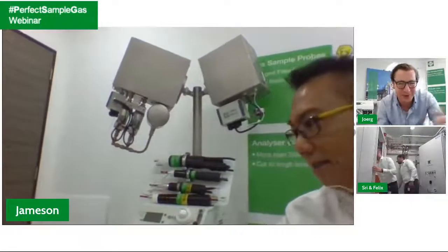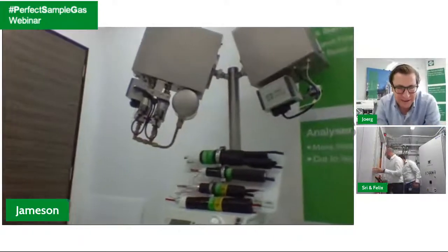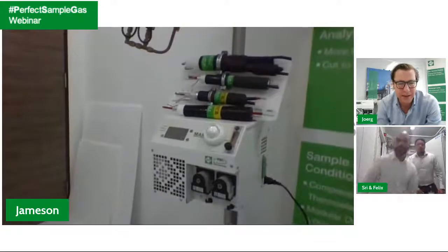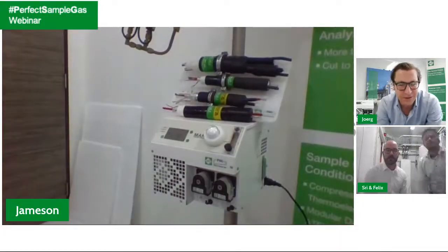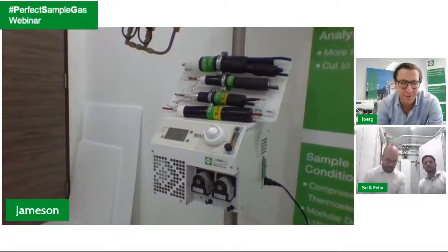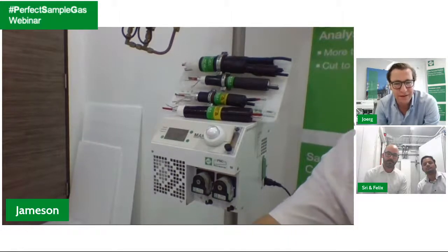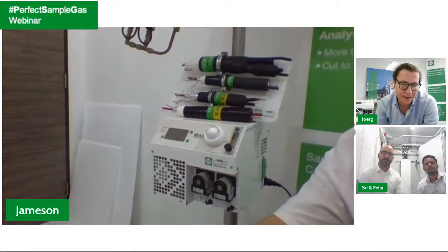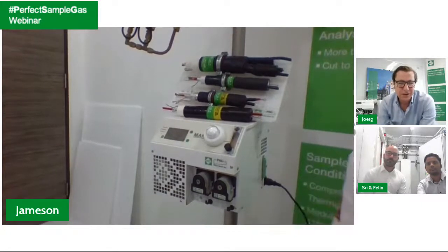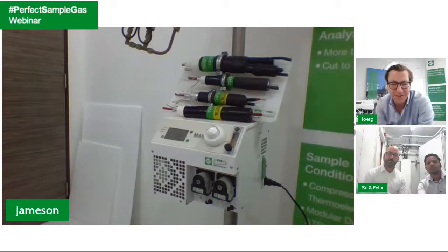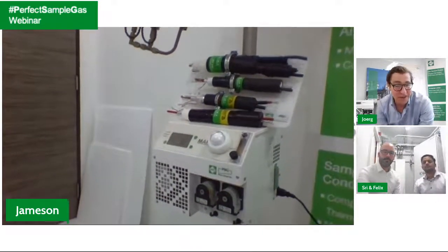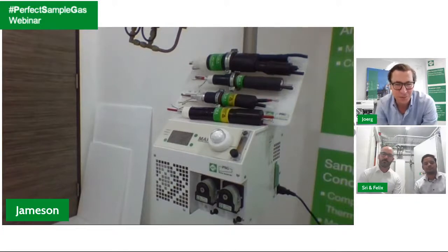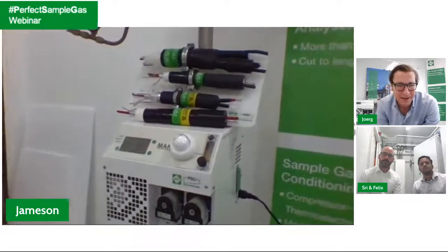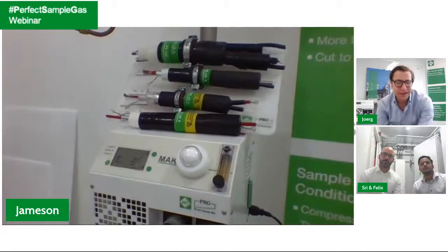This is the MAK10 cooler, and maybe we can really use this chance, Jameson. I think the one you have is pretty well equipped, and the speciality about this cooler is that it can be set up as a complete conditioning system, meaning coming with a flow meter, having a depth filter there, and like Sri said, it's a two-stage cooler. First of all, the requirement for these types of coolers is a reliable and low outlet dew point, 3°C for example, and at the same time the washout rate.